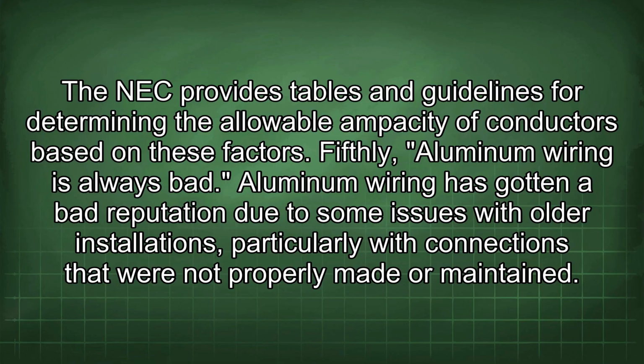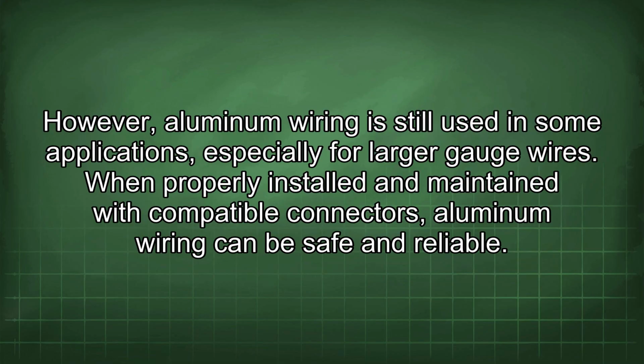Fifthly, aluminum wiring is always bad. Aluminum wiring has gotten a bad reputation due to some issues with older installations, particularly with connections that were not properly made or maintained. However, aluminum wiring is still used in some applications, especially for larger gauge wires. When properly installed and maintained with compatible connectors, aluminum wiring can be safe and reliable.